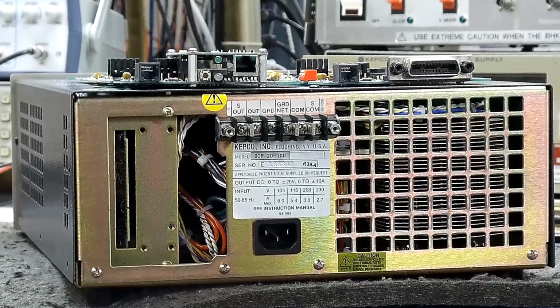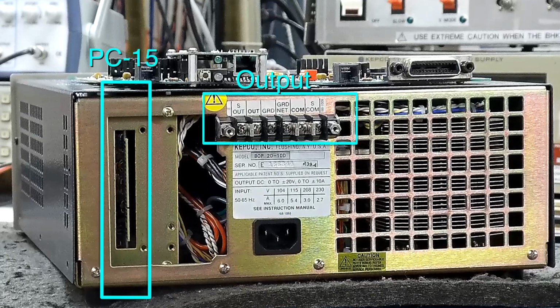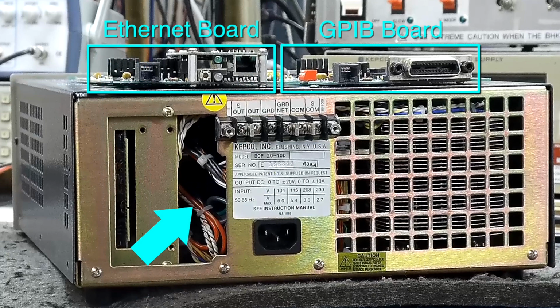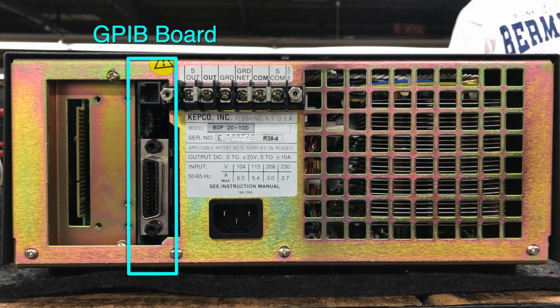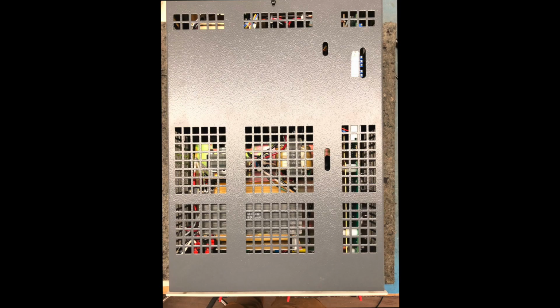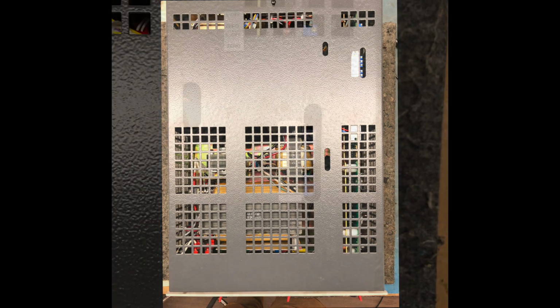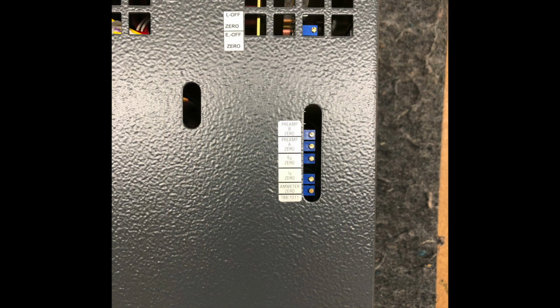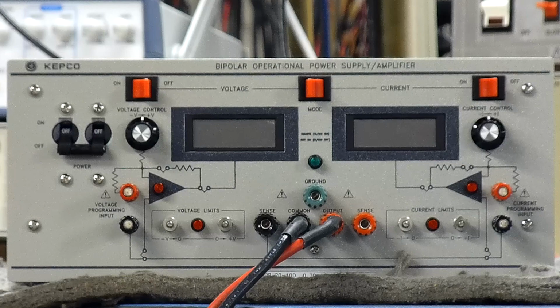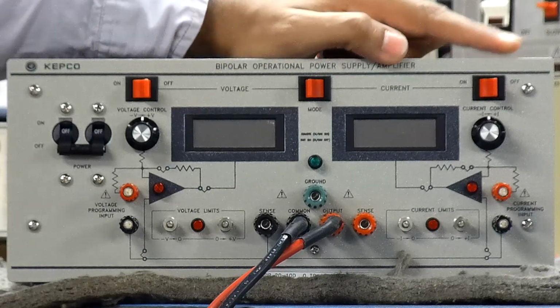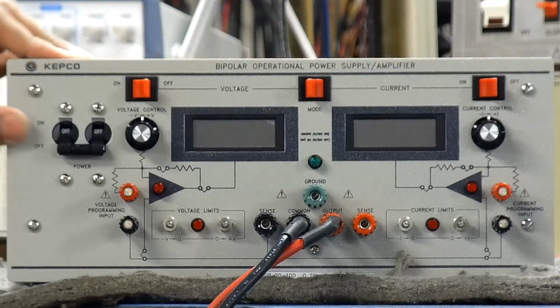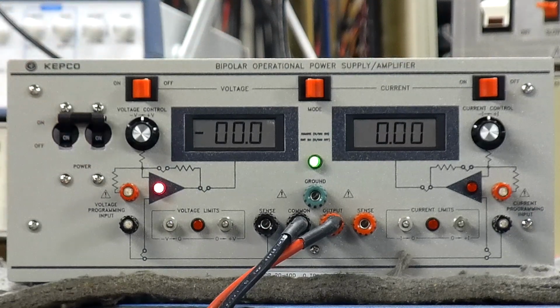On the rear, you can access the unit's output terminals as well as the PC15 connection. If a unit is ordered with the optional GPIB or Ethernet boards, the relevant ports will also be available next to the PC15 connection. At the top is access to a number of potentiometers which can be adjusted for calibration, but all units are pre-calibrated from the factory. After plugging the unit in, make sure the voltage control and current control switches are in the off position. Now just flip the circuit breaker on the front and it will power right up.